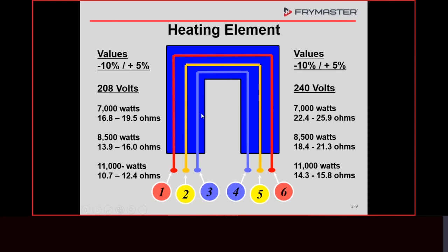Depending on the voltage, and the kW rating is going to depend on the size of the resistor, or the resistance that's used. We can check those by ohming between 1 and 6, and there are going to be 6 wires on here. The loops are 1 and 6, 2 and 5, and 3 and 4.